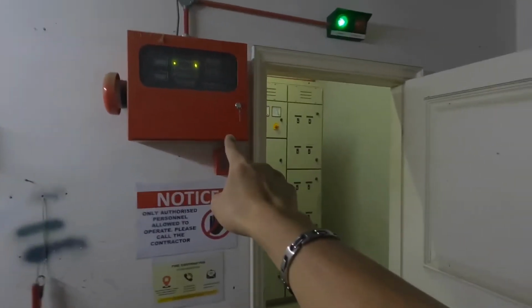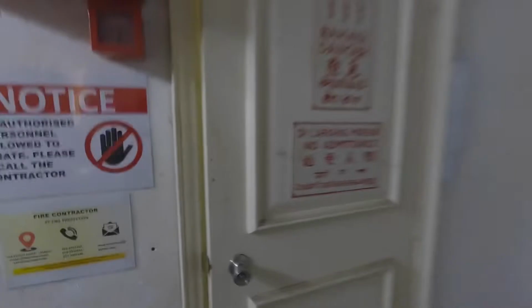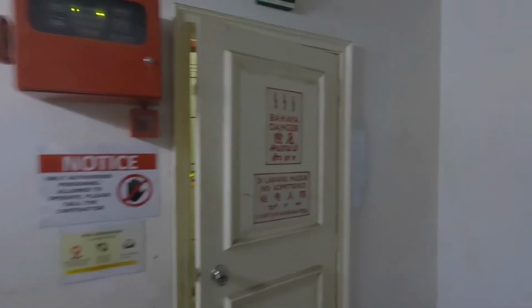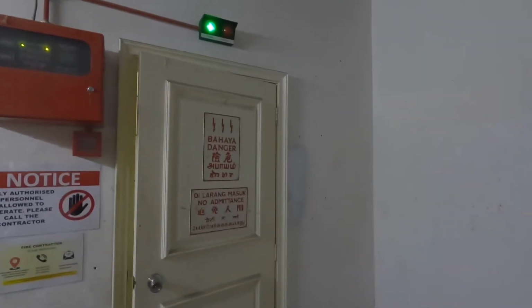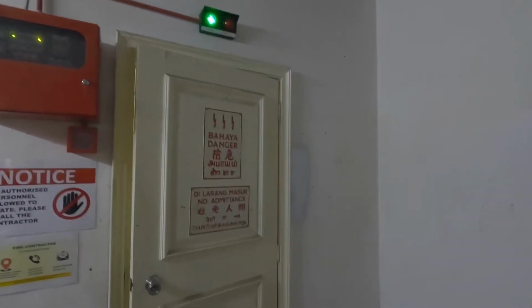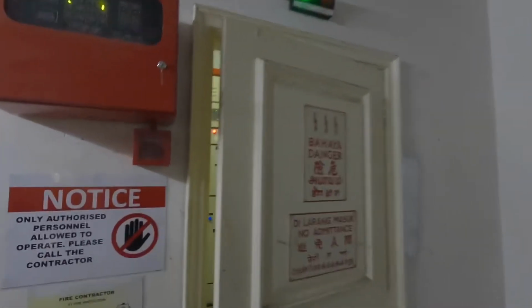Okay, inside this LV room, first of all, as we go into this LV room, this is the CO2 panel, and this is the LV room door. Okay, supposedly, according to TMB or ST regulation, it must be fire rated door. Okay, but I don't think this is a fire rated door because there's no fire rated signage written here.